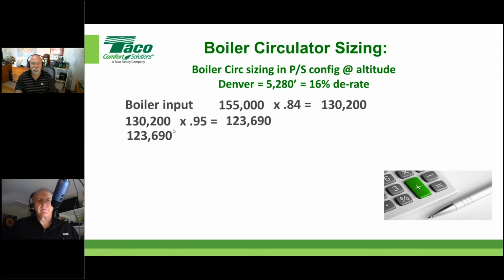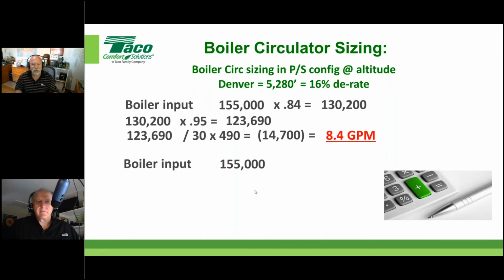I know I'm going fast, but all I do, universal hydronic formula there, I'm going to take the load, divide it by the delta T times the constant, and that tells me I'm going to need 8.4 gallons a minute. Look at that. 8.4 to do a boiler that most people would throw a 15-gallon a minute pump at. You see where this is going?